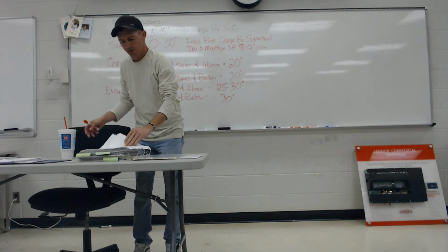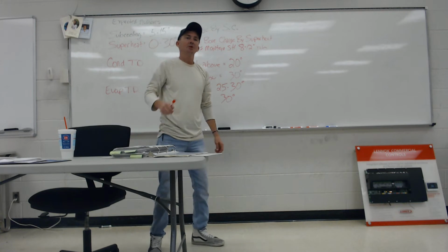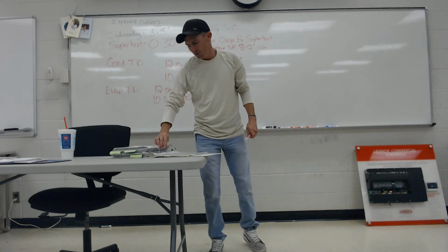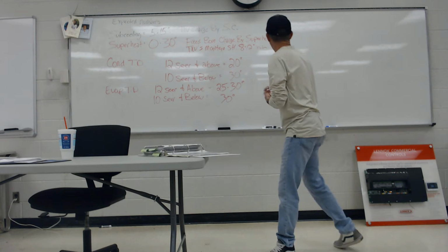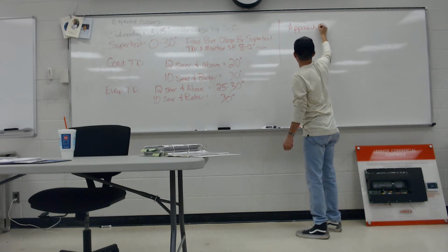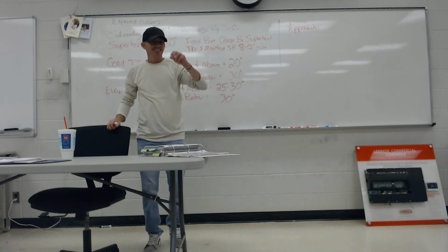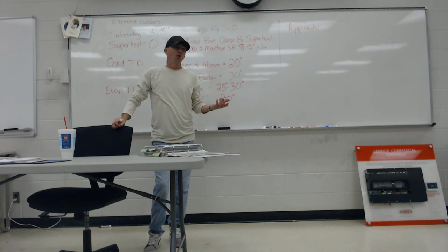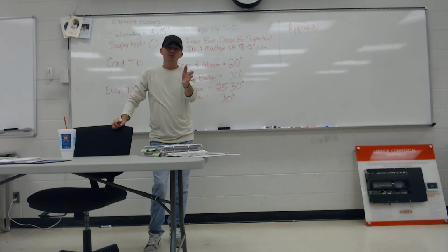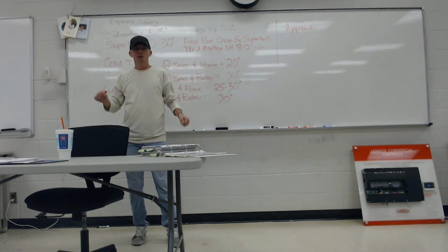I'm going to throw one more up here. Lennox. A lot of you guys did some Lennox work, right? Big Lennox dealer, huge. Lennox loves to use the approach method on their air-to-air stuff. You've seen it on all the charging charts, right? On the older Lennox stuff, in the 90s, early 2000s, mid 2000s, everything was approach. It wasn't until recently they started doing both: here's the approach, here's the subcooling.